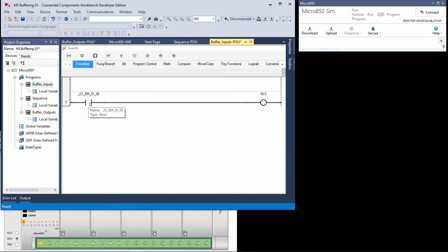Now with this controller, you're not really worried about that. But with ControlLogix and CompactLogix, that's not a remote possibility, that's a definite possibility. And when you write your code, you may not realize this yet, but as you go down and write your code, because of how the scan is sequenced, you are depending on any input staying in the same state as far as your program's concerned for the whole program scan.